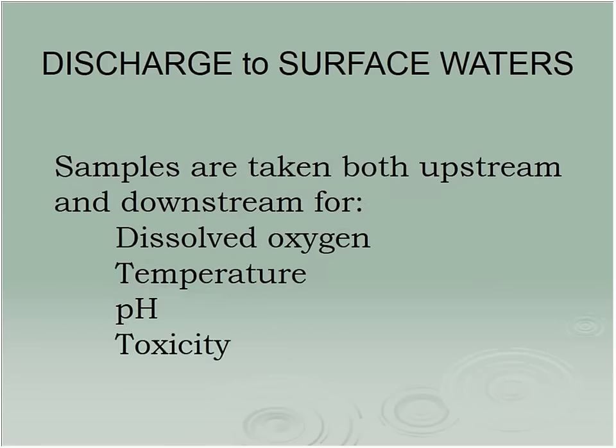The other thing that occurs, the testing for various things, is what they call whole effluent toxicity test. Are you familiar, ever hear of that? It's a strange thing. We would do it quarterly, and what we would do is we would take water from upstream from the river, and then we take our water and we send it off to a lab, and they would test it. What they do is they keep making increasing concentrations of our wastewater into the river water, and they would test for Ceriodaphnia, which is a water flea, and fathead minnows, and they could go until our wastewater would kill 50% of them. It's a fun job, huh?